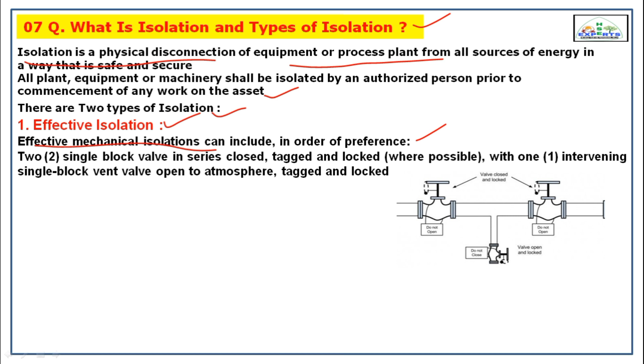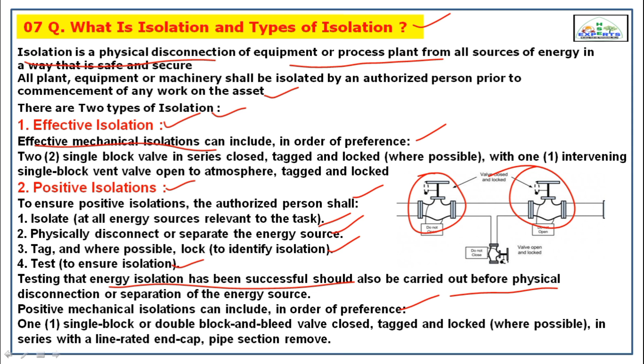Positive isolation. To ensure positive isolation, the authorized person shall isolate, physically disconnect or separate the energy source, tag and, where possible, lock, and test. Testing that the energy isolation has been successful should also be carried out before physical disconnection or separation of the energy source. Positive mechanical isolation can include, in order of preference, one single block or double block and bleed valve closed, tagged and locked in series with a line-rated end cap or pipe section removed.